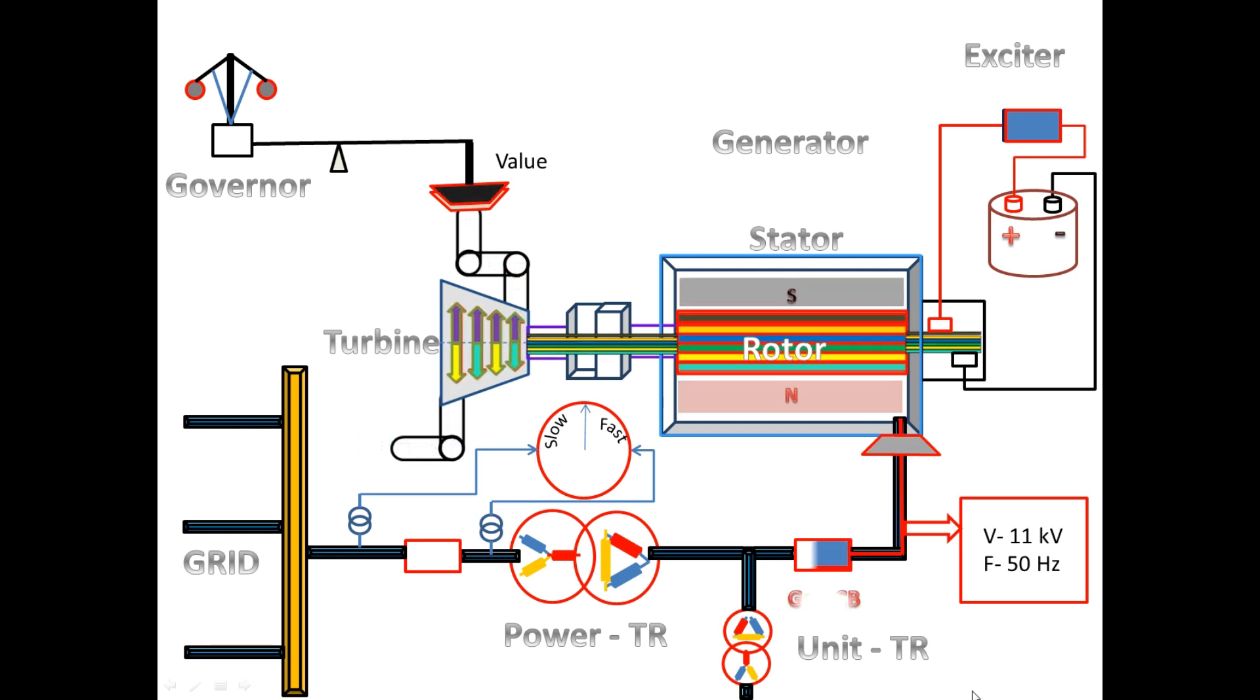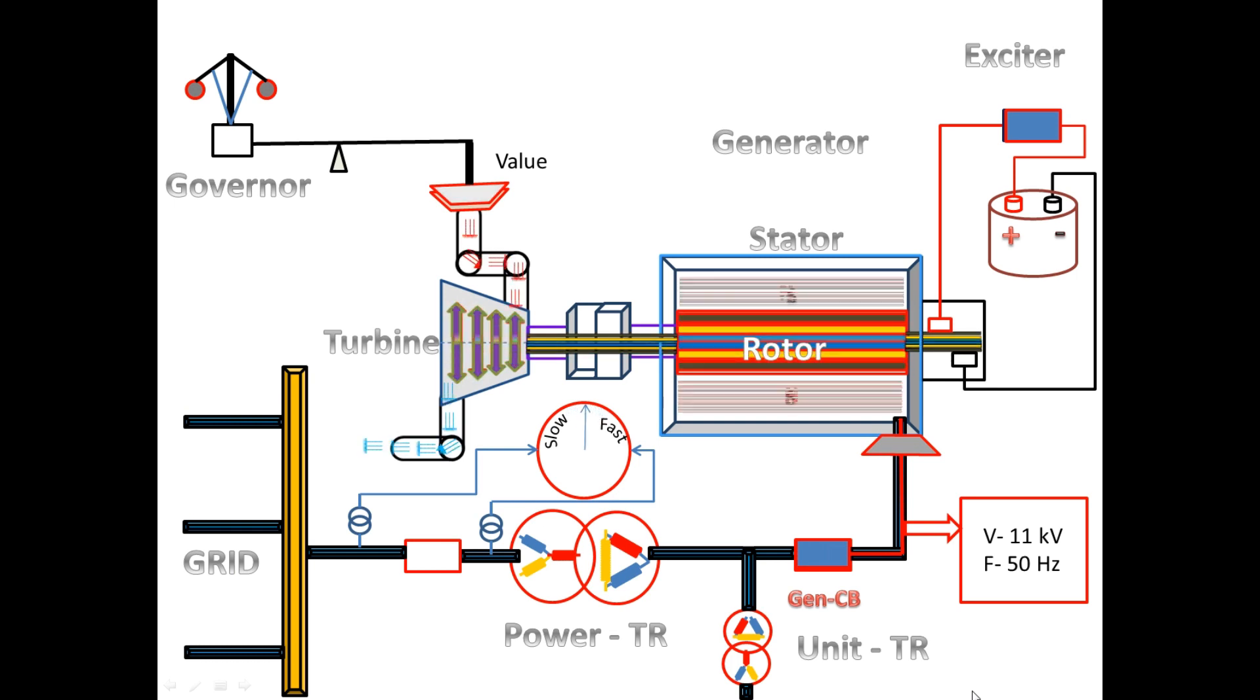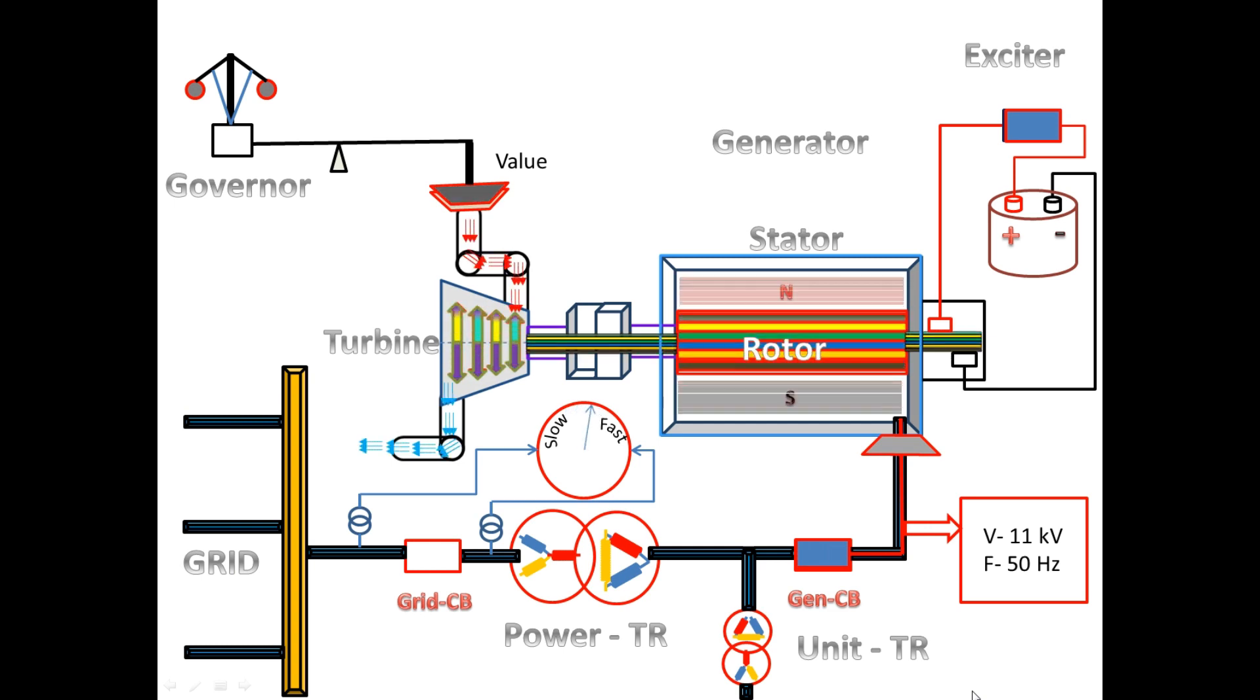When the generator breaker closes, the unit transformer and power transformer get power supply. To close the grid breaker, we have to check synchronizing between the grid and power transformer.